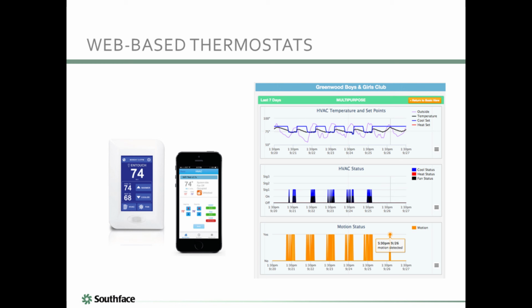Web-based thermostats also provide a feature where you can set the occupant adjustment range and lock out the device with a passcode. Occupants are able to alter the set point by a predetermined amount, but they can't go beyond it. You can also allow occupants to set a hold duration so that they can turn on heating and cooling after hours for a limited period of time.